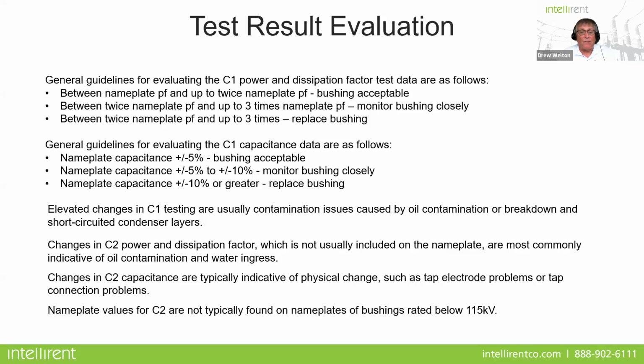5% to 10% means, again, monitor very closely. And then anything greater than 10% means you're going to replace that bushing. So elevated changes in the C1 tests are usually contamination issues, and that's caused by oil contamination or breakdown in short-circuited condenser layers. Changes in C2 power factor, which again is not always included in the nameplate, are most commonly indicative of oil contamination. So what do we do if we don't have a nameplate for C2?